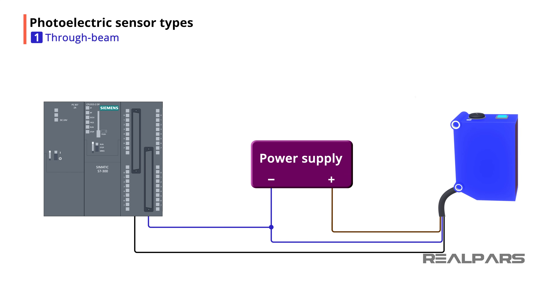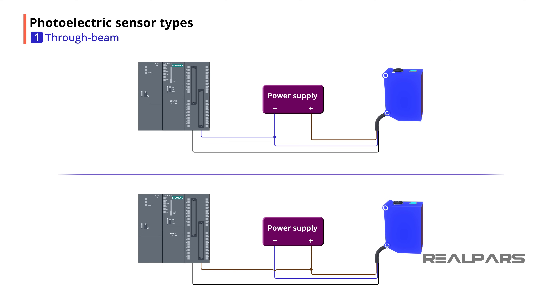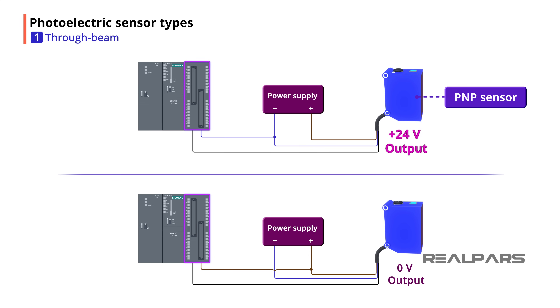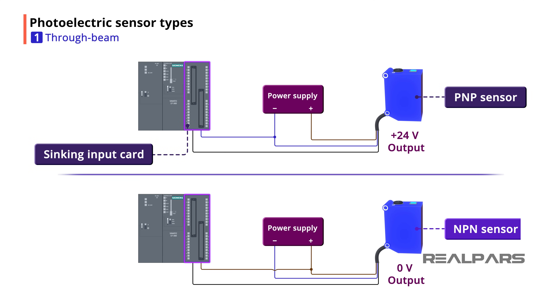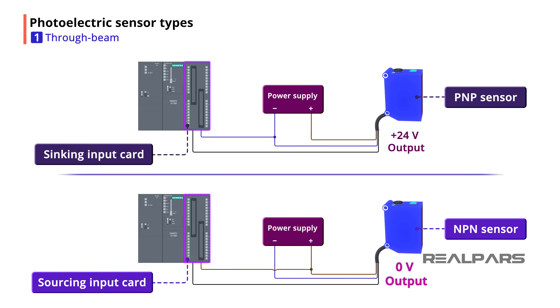The sensor's output is the signal from the sensor to the PLC. Depending on the sensor, the output can be a positive signal or a negative signal. The type of sensor output signal you will use depends on what type of PLC input card the sensor is connected to. For example, if the sensor is PNP, meaning it has a positive output signal, the sensor's output wire will have to be connected to a sinking input card. If the sensor is NPN, the output signal is negative, and the output wire will need to be connected to a sourcing input card.